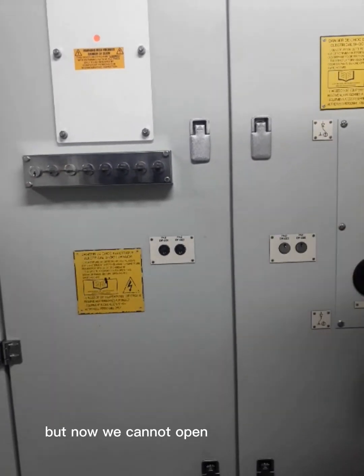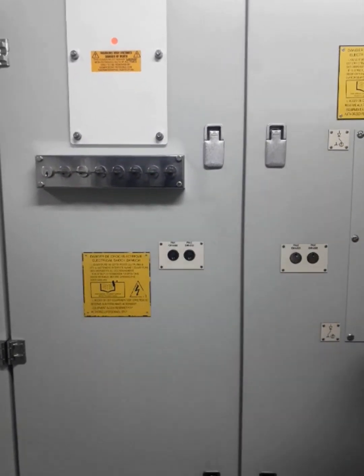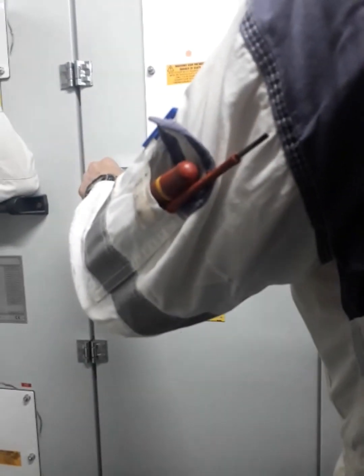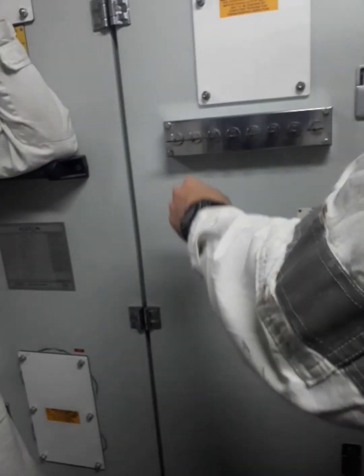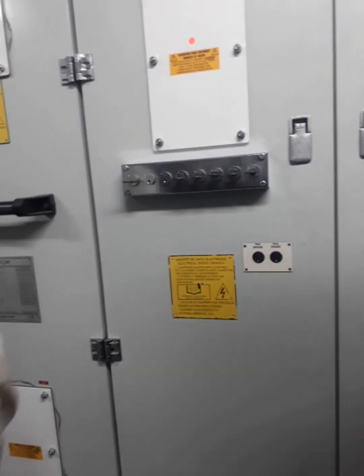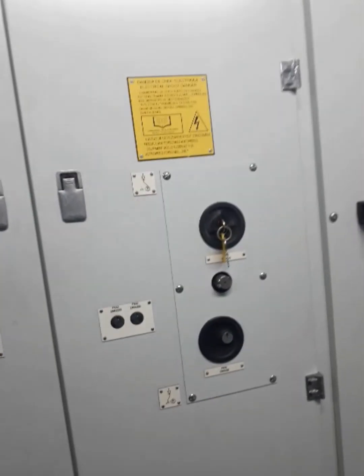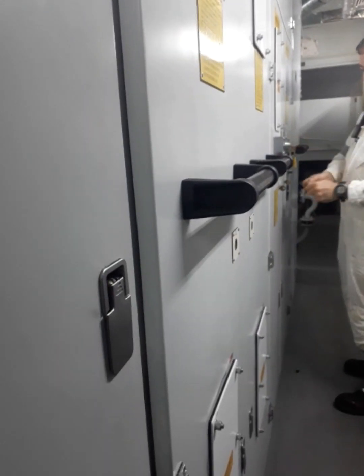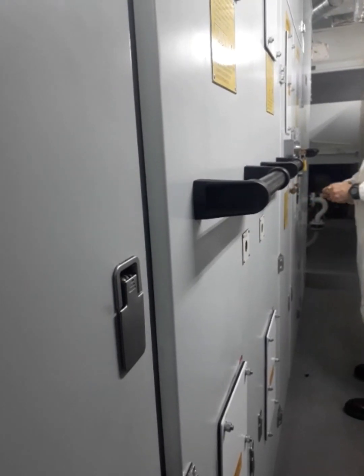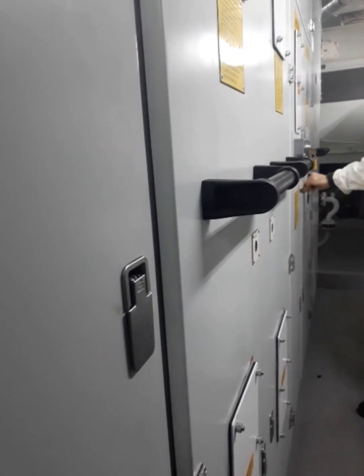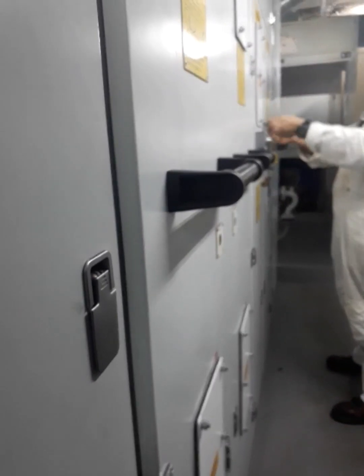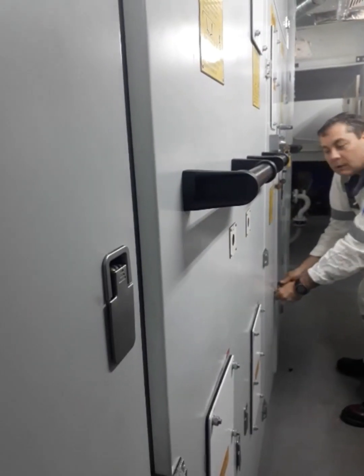But now we cannot open the door because we need key. 4 key we need here to open these doors. How are we going to take the key? We install this one. We take 2 keys. These 2 keys are going to the other side. 41, open, 41, open, and now we are allowed to open the doors.